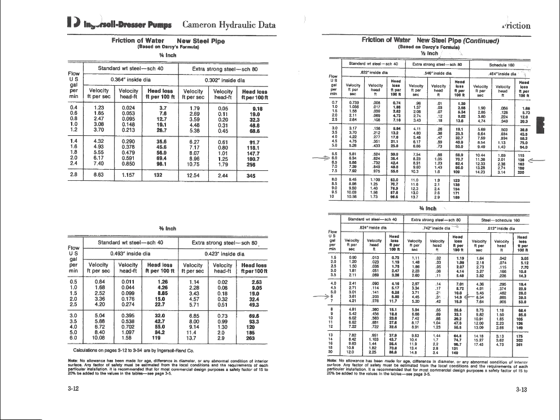This is quite large compared to our static head of 3 feet. So this justifies the previous comment I made about using a larger pipe size. If we use a three quarter inch nominal pipe size for the same flow rate using schedule 80 pipe, which has an inside diameter of 0.742 inch, we get a head loss of 14.9 feet per 100 feet of pipe, or a friction loss of 1.49 for our 10 foot pipe. So as you see, doing a flow schematic and sizing a pump go hand in hand.